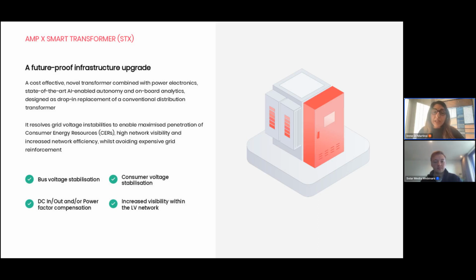We also have a number of data sensors in this device that allow us to do two things. One is monitor the performance of the asset and keep an eye on its health. Therefore, we're able to prescribe a condition-based maintenance regime for network operators that allows them to save cost through the life of these assets, as well as proactively detect any faults that may occur that can lead to downtime. So we maximize uptime by identifying any anomaly that needs to be flagged to the network operator around their asset base.